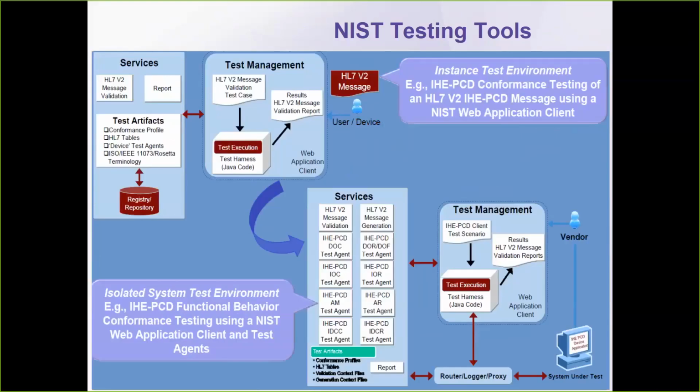The messages PCD vendors produce and consume can be put into the tools, and we can see here a general path for the automated validation process within this diagram. A report is generated for each test vendor registers in their system that they're registering for, which can be copied by the tester for reference locally if needed, which can be useful.